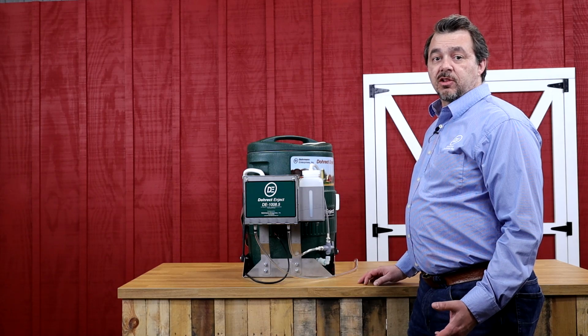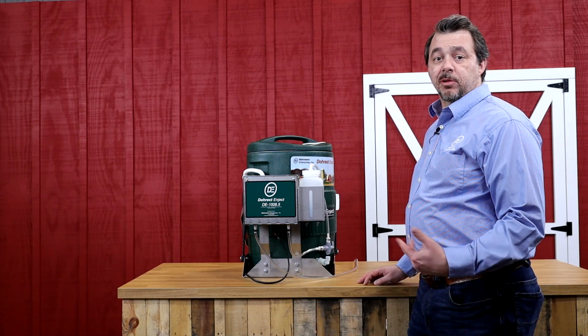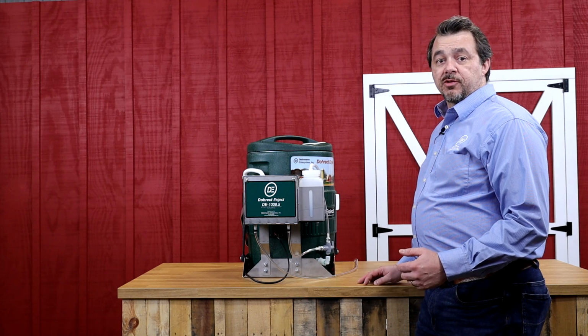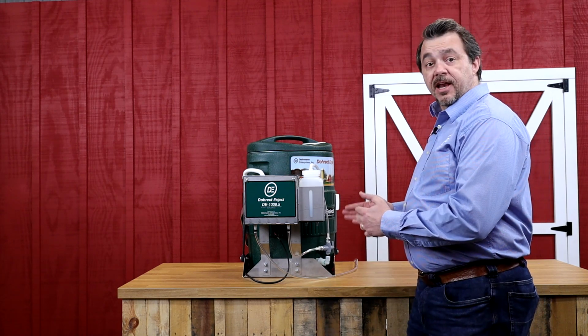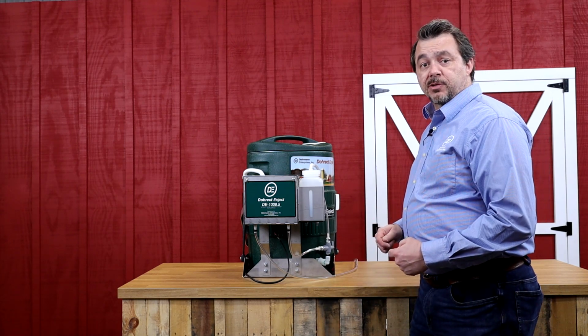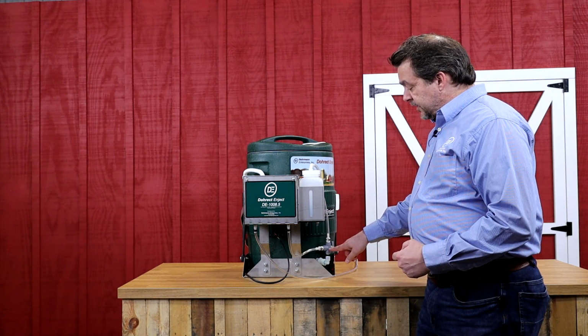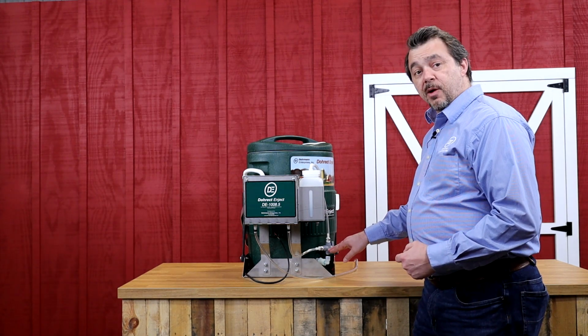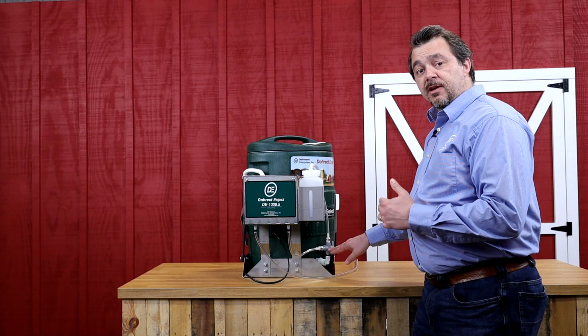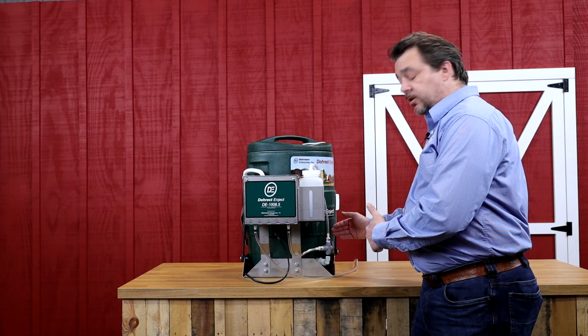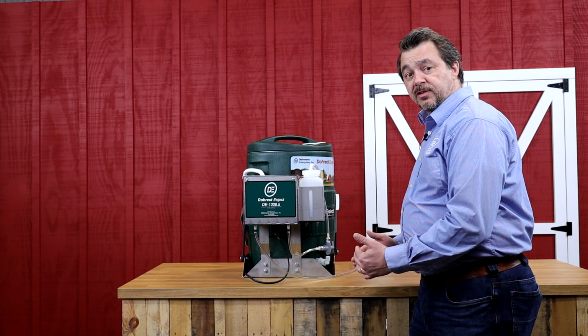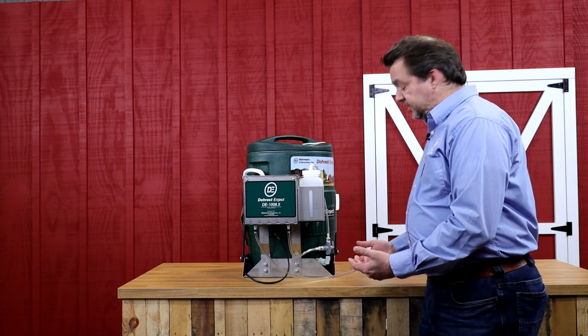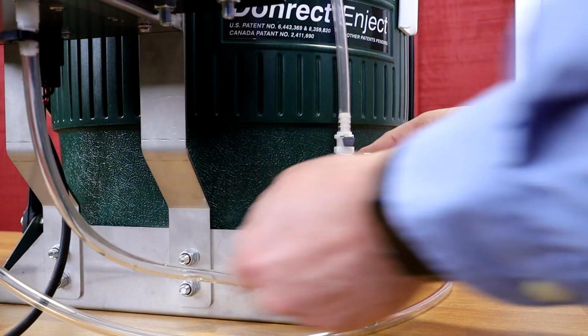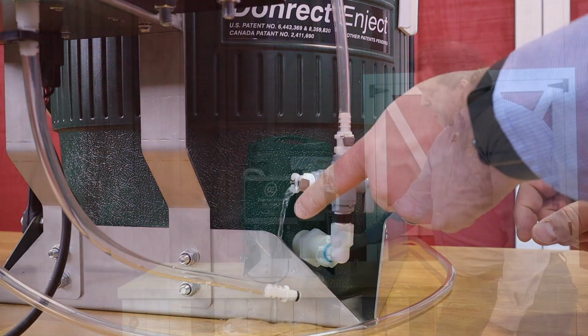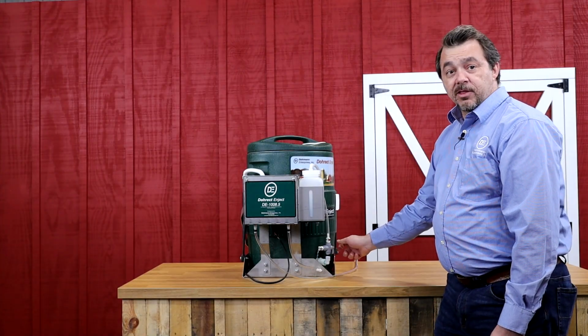Next, we want to start taking a look for any potential areas that might be plugged. So to do that, we're going to go through the system and check connection by connection. So the first place we're going to want to look at is right down in this valve assembly. We want to make sure that we have product flowing freely from inside the cooler to the outside of the cooler through the valve assembly. The easiest way to check this is by simply disconnecting this hose and then taking the valve handle and flipping that down. And if everything goes right, you should have product coming through there.